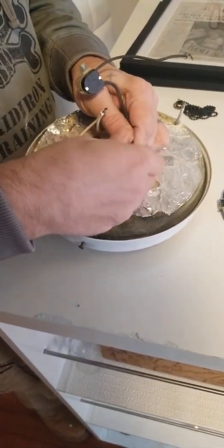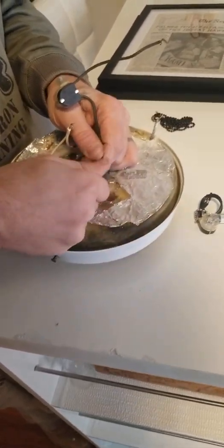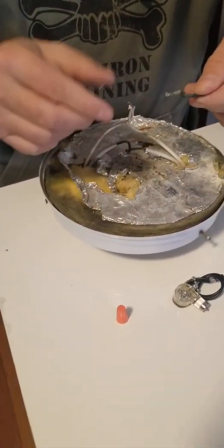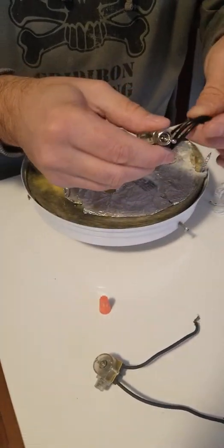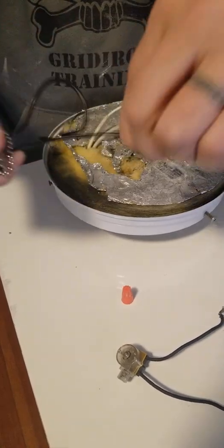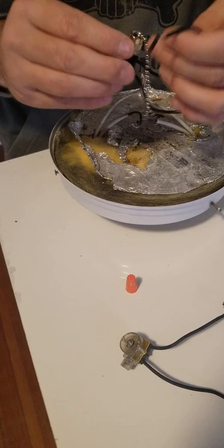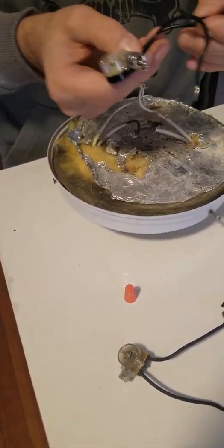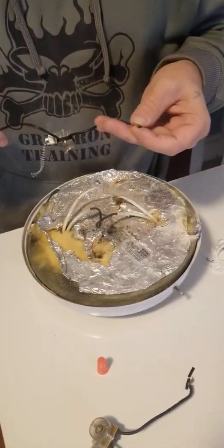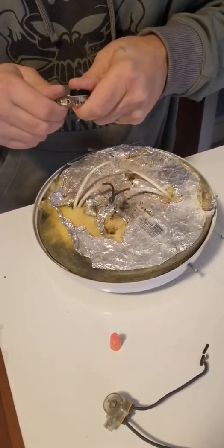So I'm going to go ahead, very simply, just disconnect it from the black. This lead was going up, continuing the circuit through the ceiling. Very simple — we just remove this. And when we replace it, we don't have to worry about which one goes to which, whether black goes to black or to white, but it doesn't matter when you're doing a switch like this. It's just an interrupter basically in the electrical current — when you switch on and switch off. So what we do is run your piece and screw this.